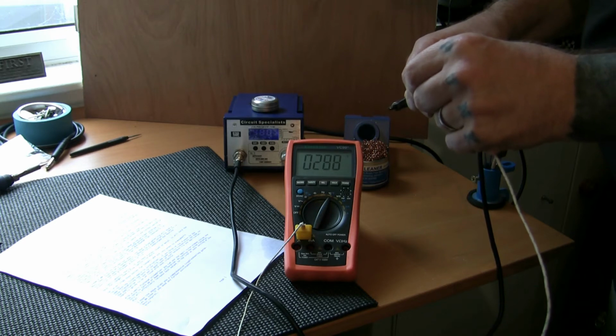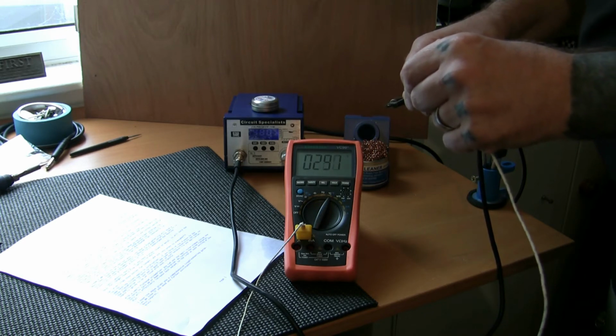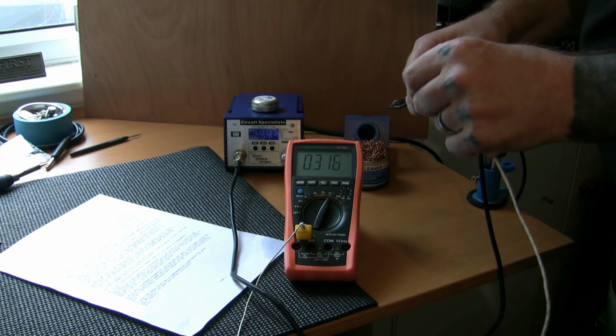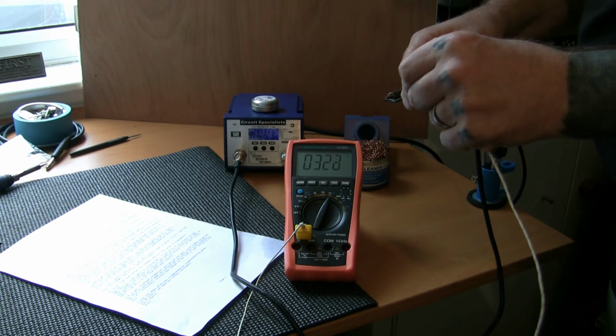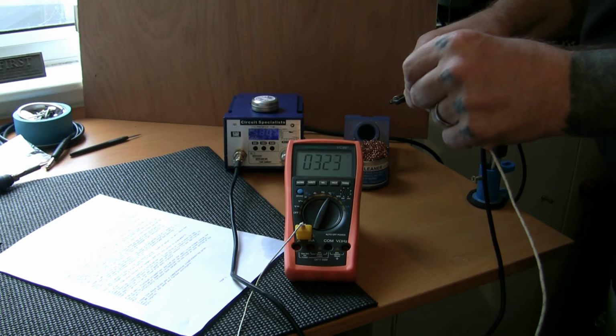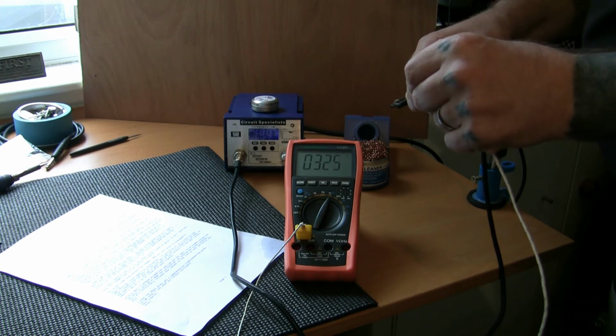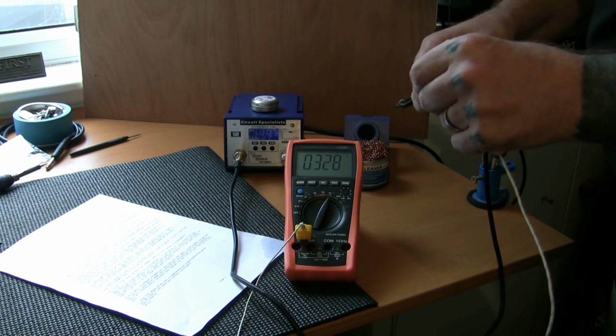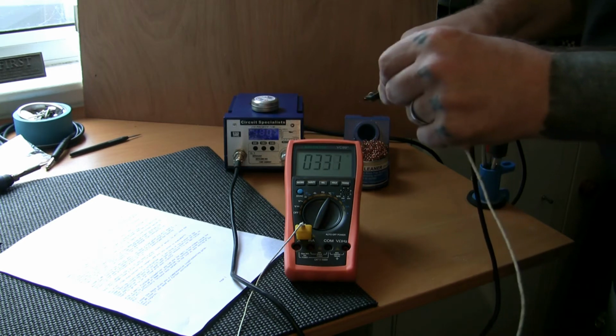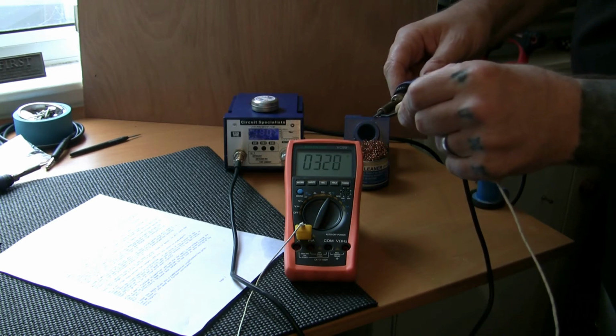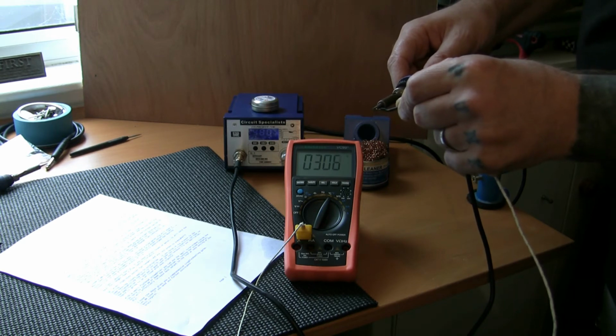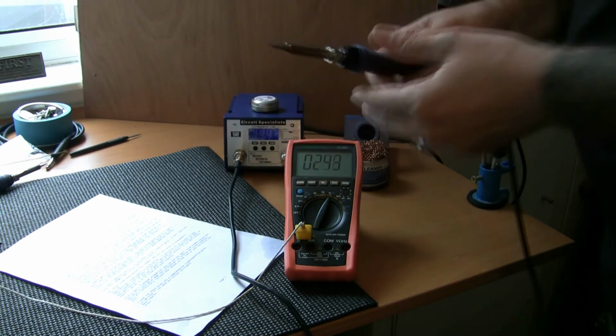Do you see it? So we're getting about 290 there. Come on, it's 300, 320. So it's maxing out at about 320, look. 317, 318, 320. So on a reading on the multimeter of 324, 325 degrees, my CSI Premier 75 watt is showing 480 degrees. There is a problem. That's the best we're going to get.